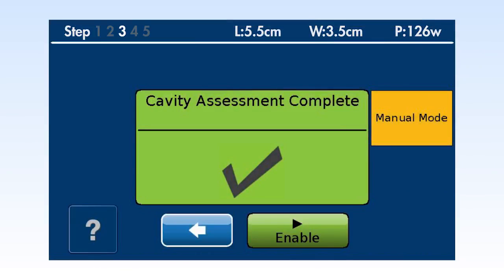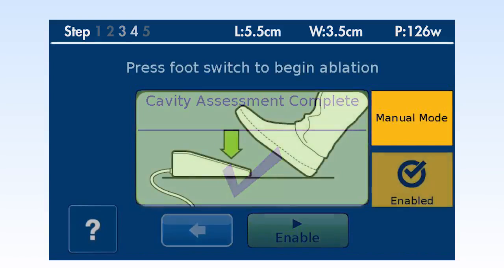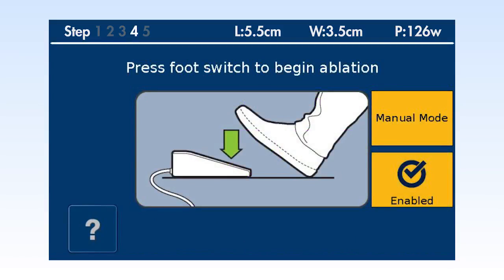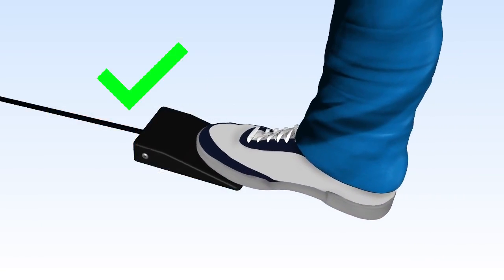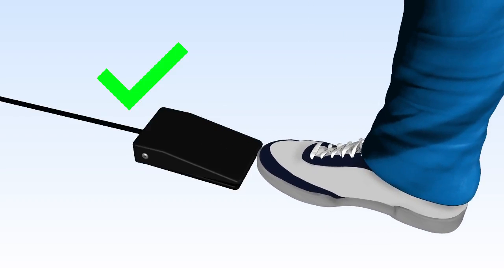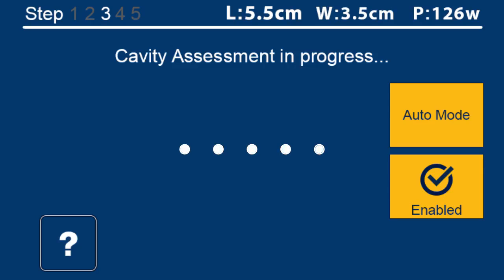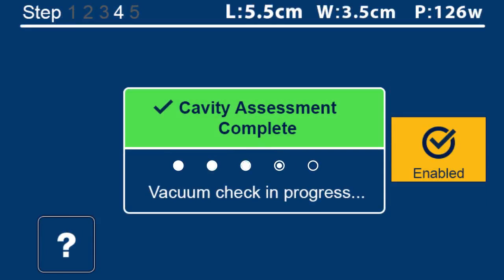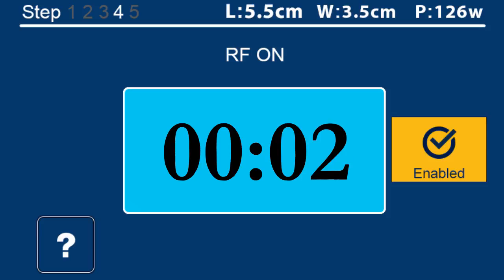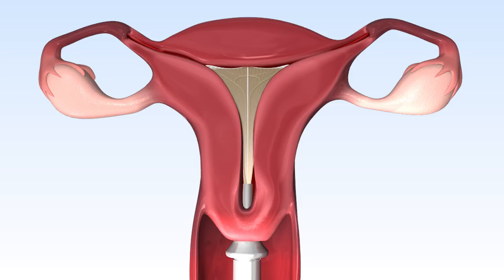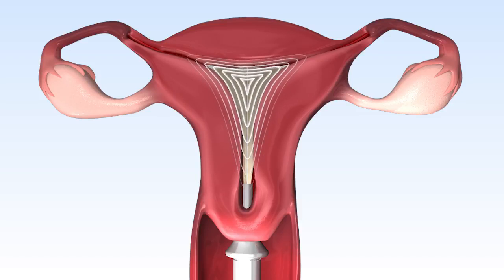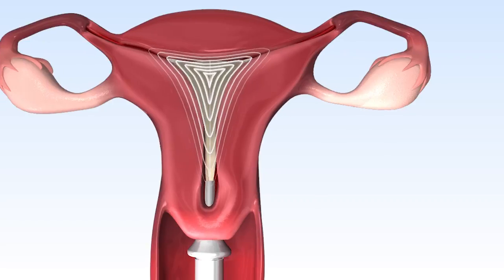Once the CIA test is complete and has been passed, press the Enable button. The ablation will not start until the physician depresses and releases the foot pedal again. In the automatic mode, the ablation cycle will start automatically upon successful completion of the cavity integrity assessment. During the ablation, the patented moisture transport system helps maintain contact between the array and endometrium and removes any excess fluid byproducts from the uterus.